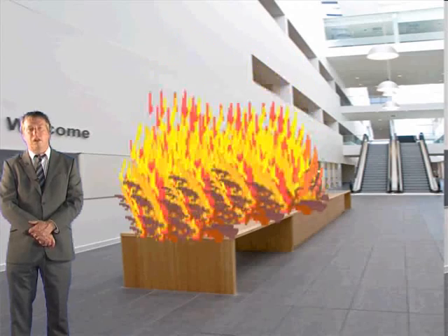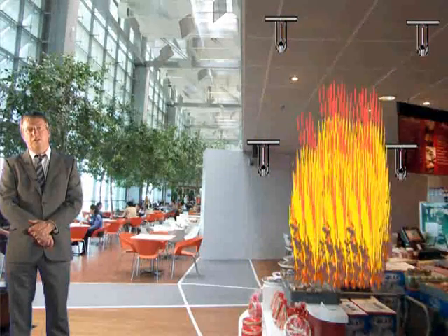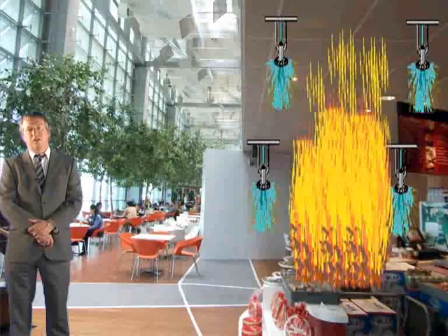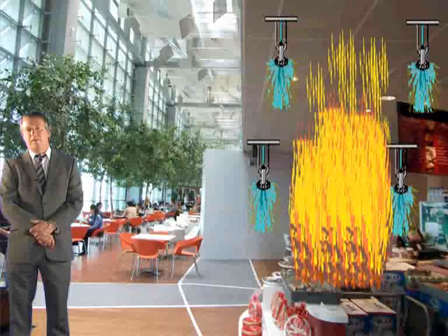The physical area of the fire is related to either the sprinkler spacing or to the size of an isolated package of fuel, such as a reception desk in an otherwise empty atrium. The Smoke Control Association gives various accepted conservative areas for fires in different types of premises. For most normal risk premises, a fire is expected to be contained to a size no larger than the space between 4 adjacent sprinkler heads in any array.